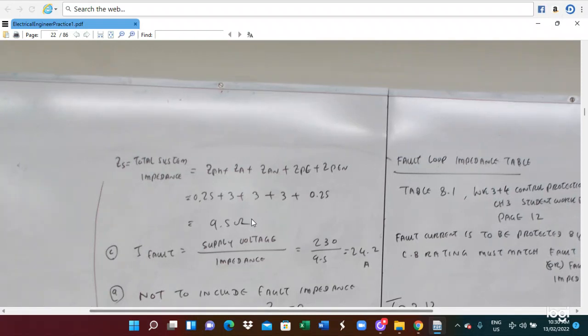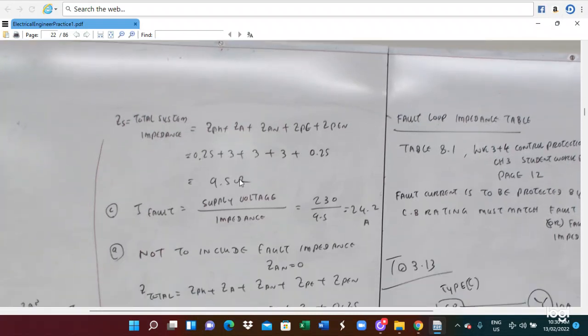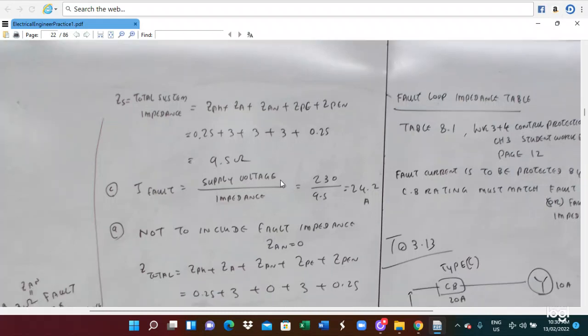So Zph, Za, Zan, Zpe, Zpen. So this is the thing we add. So this is the 9.5 ohm. So if you get the fault loop impedance, you can also calculate any fault current. When the electrical fault happens, the current can be calculated. Supply voltage divided by impedance. Supply voltage by impedance, then you can calculate the fault current.